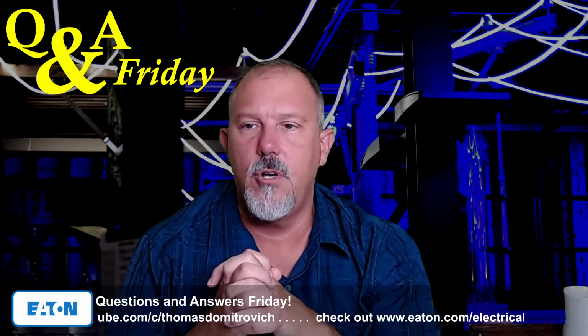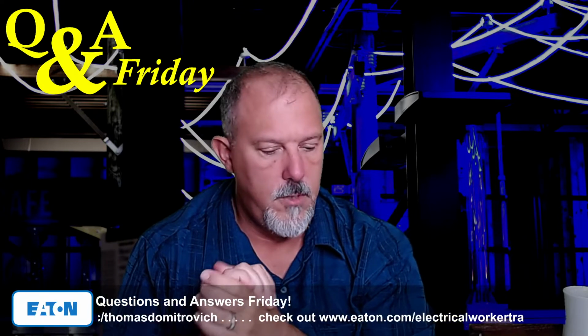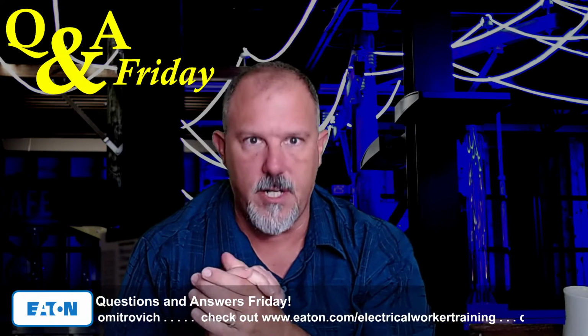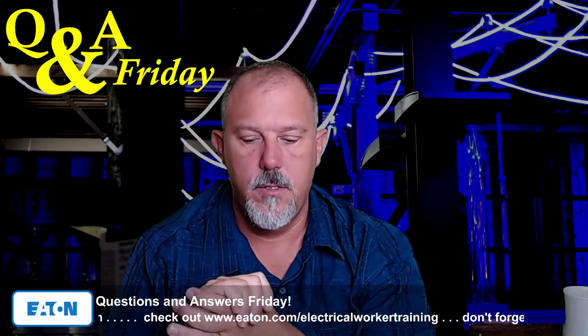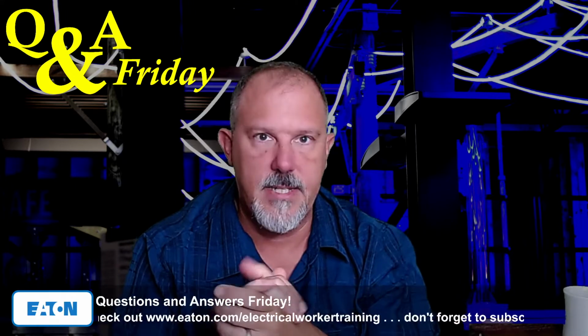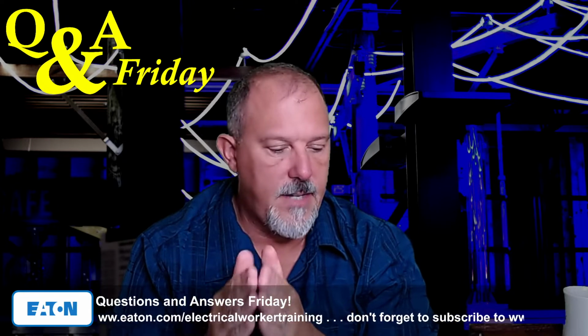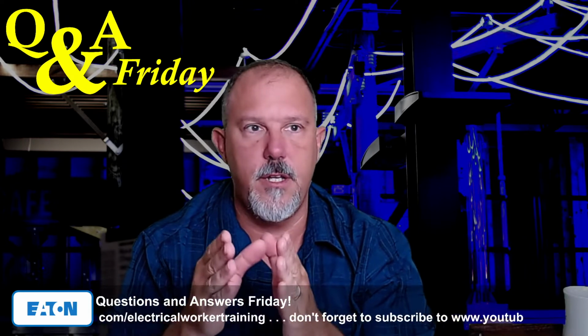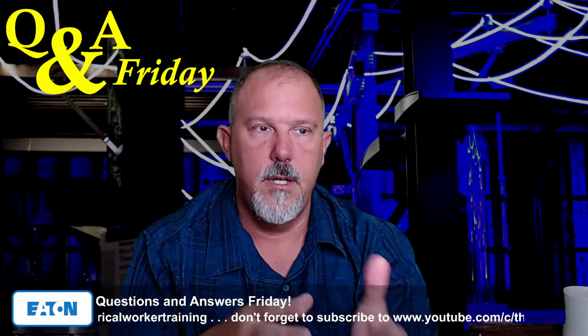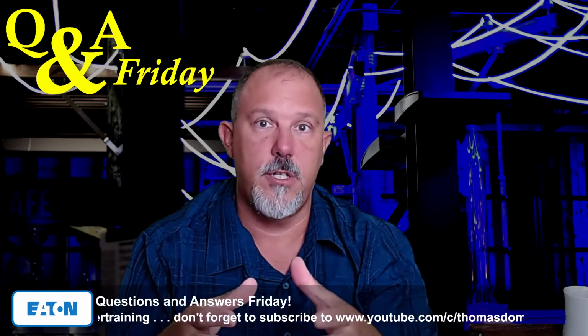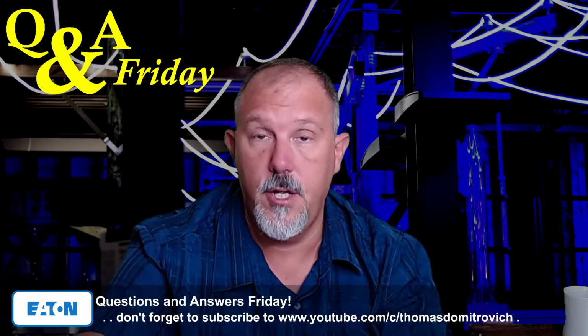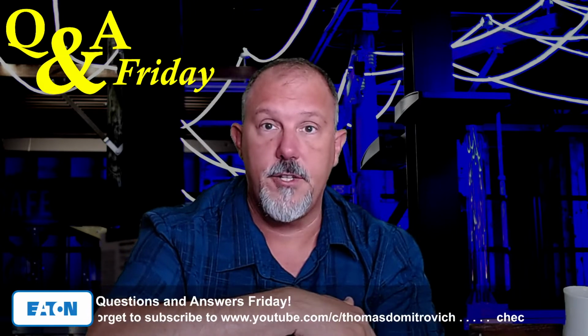240.87 is not about overcurrent protection. 240.87 is about arc flash reduction. So you still need to have 240.87. It's not about protecting the conductor. It is about arc flash reduction. That's why we compare the arcing currents to ensure we're reducing arc flash.